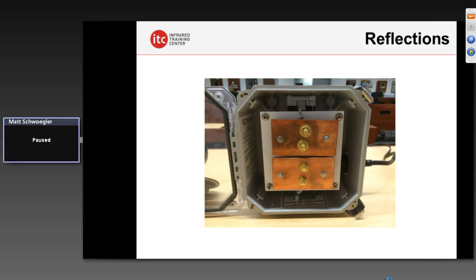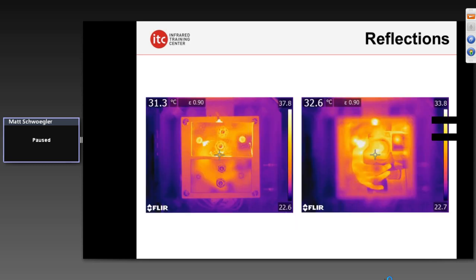One of the labs we use in our training room is this bare metal bus bar lab — two little pieces of copper bus, with a resistance heater inside so we can heat the surface up and evaluate it with the infrared camera. It's a great lab to demonstrate both emissivity and reflectivity — showing how reflective the thermographer can be and how that shows up on the surfaces you're trying to inspect. On the left here is an image that's well focused, what you'd normally capture in the field. On the right, I've focused on the reflection, and you can see thermal patterns of my hands, the camera, and even the tripod, all picked up off the surface of this mock-up of bus.